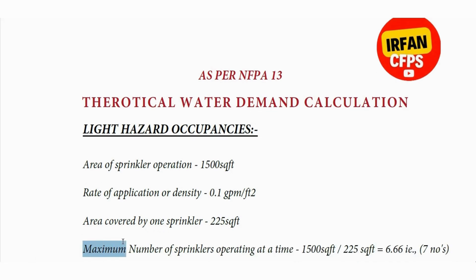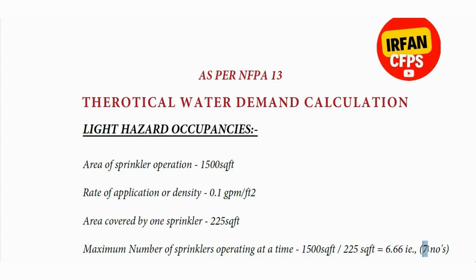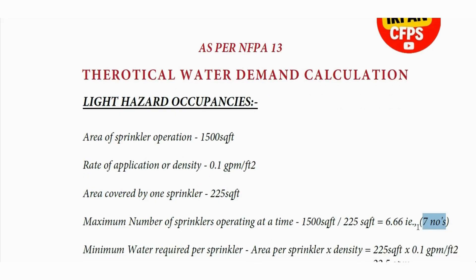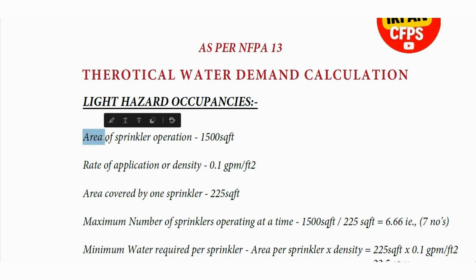The maximum number of sprinklers operating at a time is calculated using the formula: total design area of sprinkler operation divided by area covered by one sprinkler. This gives us approximately seven sprinklers. So the total number of sprinklers operating simultaneously in the design area will be seven.